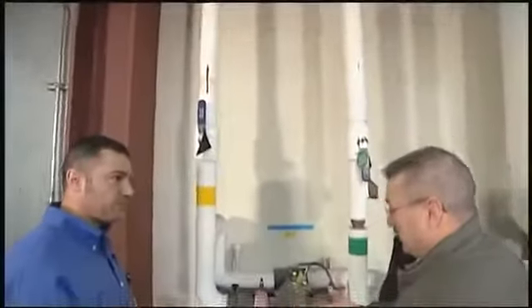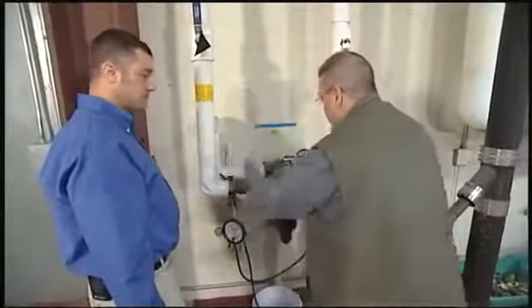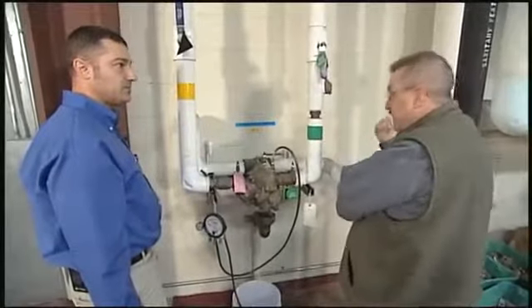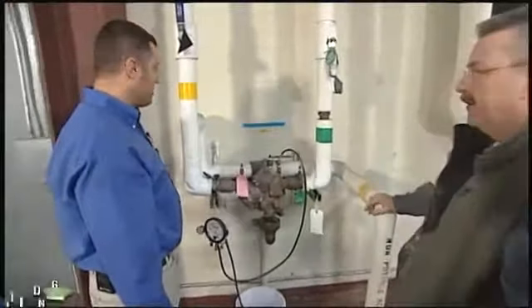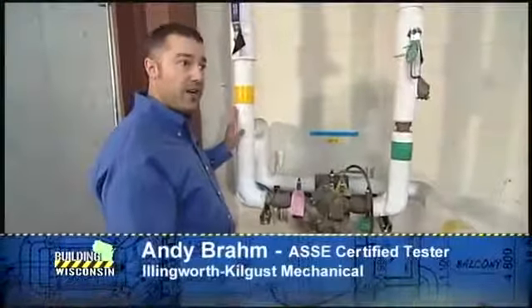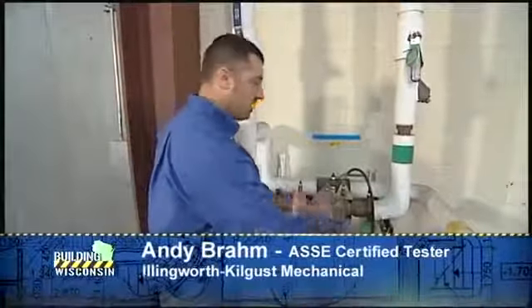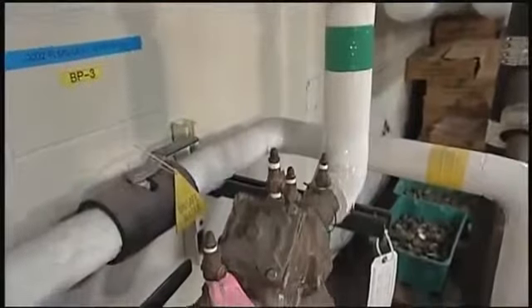And because there's glycol mixed in here, and again, in any other commercial building, it might be acids or a lot of nasty stuff. If you didn't have this device and you got maybe a negative pressure on this side, it could suck all that back into our water supply? Yep, you can get back pressure from the equipment maybe creating pressure, which is pushing it through, or you could get like a water main break, which would suck the water through, and this valve's going to stop that from happening so that we don't have to have all that nastiness in our good potable water.